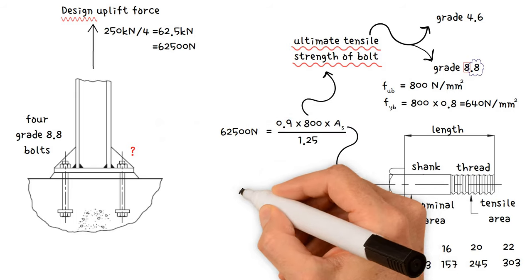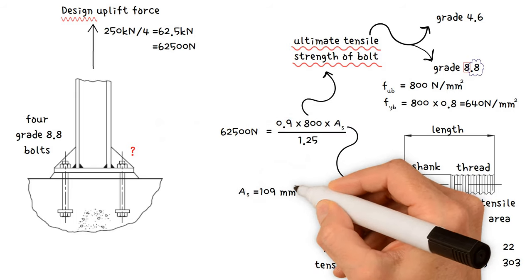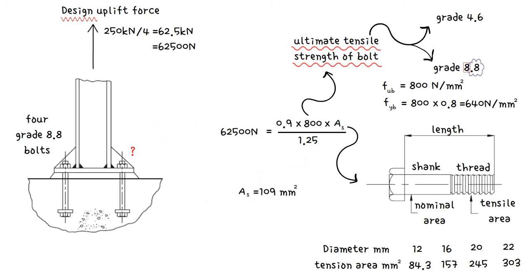Therefore, the bolt tension area equals 109 millimeters squared. As a result, we should use 16 diameter bolts, tension area 157 millimeters squared.